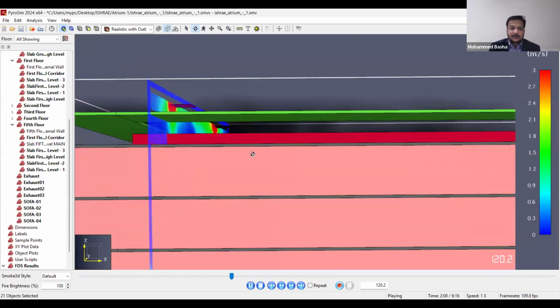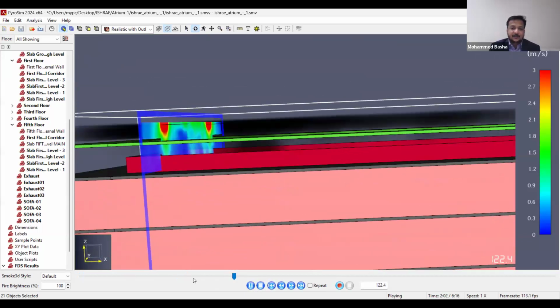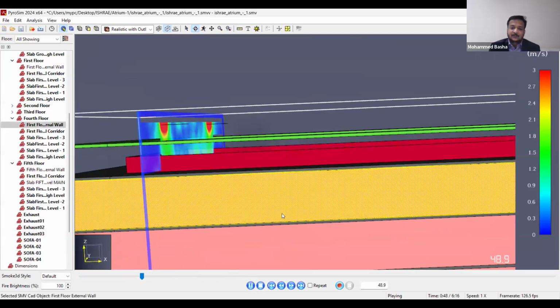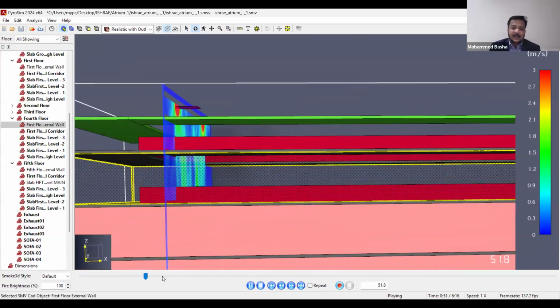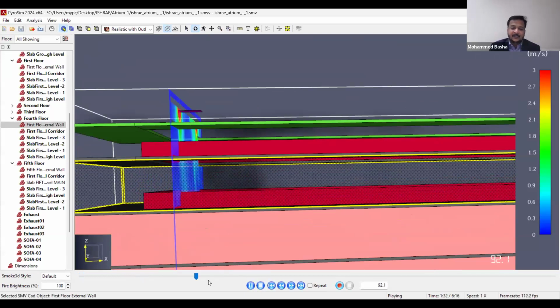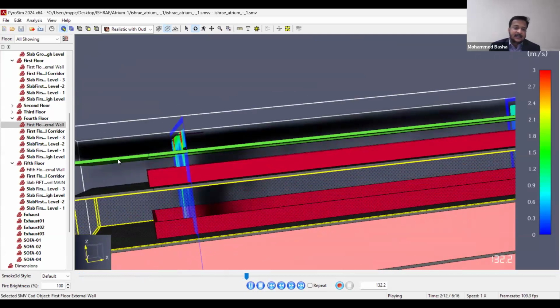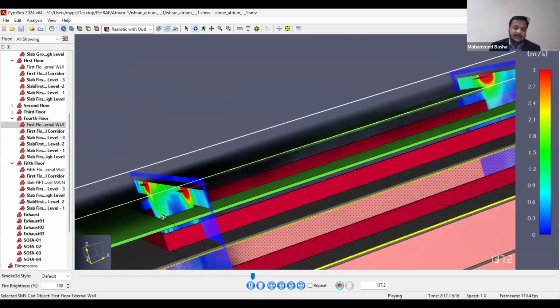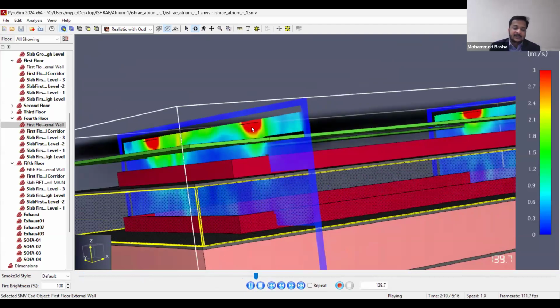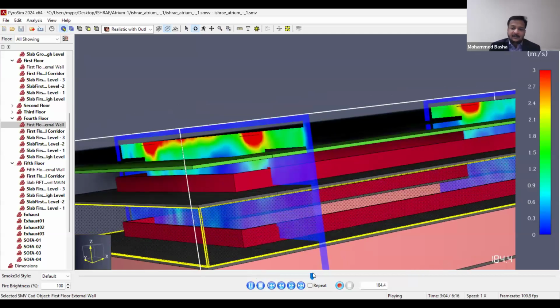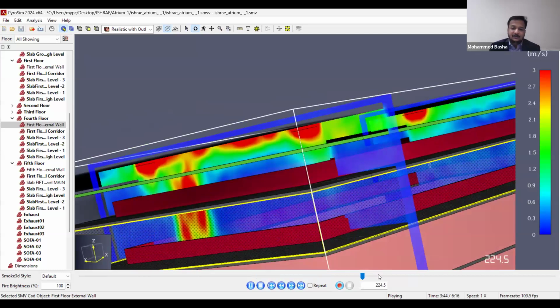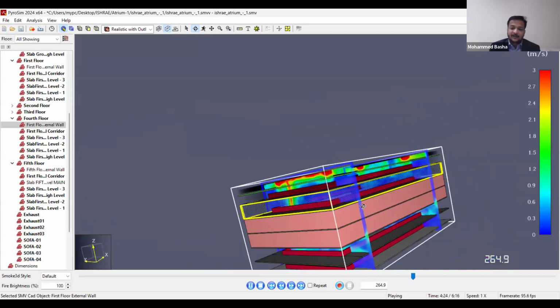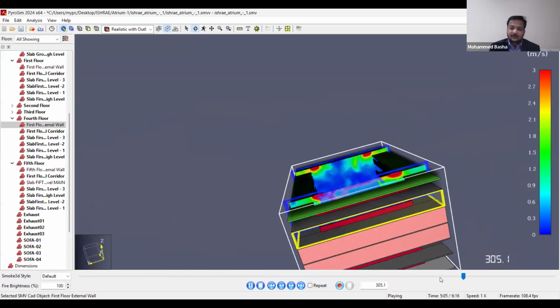And the smoke, as I told you, first hits the ceiling. You can see the phenomena, how it's developing. As I told you, the smoke will not disperse radially out. It has to hit the ceiling first. Then it will slowly start to come down. The green line I mentioned is the 1.8 meter tenable height. All 4 extracts are running. You can see the velocity of the extracts is around 3 meters per second. But my smoke comes down. I'm not having a tenable environment. Let's see, I will show you when it goes down fully.